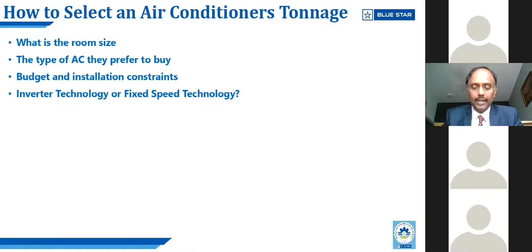A very quick thumb rule: there are 3 zones as I mentioned, in a hot climate and a hot and humid climate, you can take anywhere around 110 square feet per ton. So if it's 1,000 square feet, divided by 110, roughly gives you 9 to 10 tons. But in a mild climate zone like Bangalore, Pune, or Guwahati, you can go up to 150 square feet per ton.